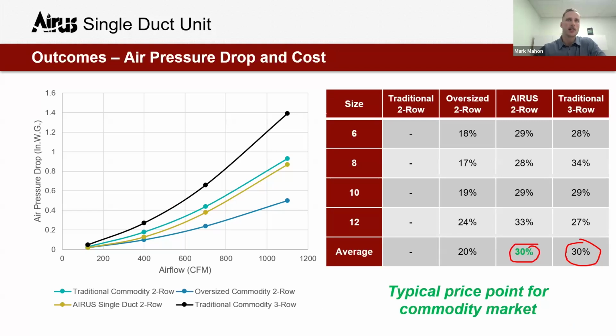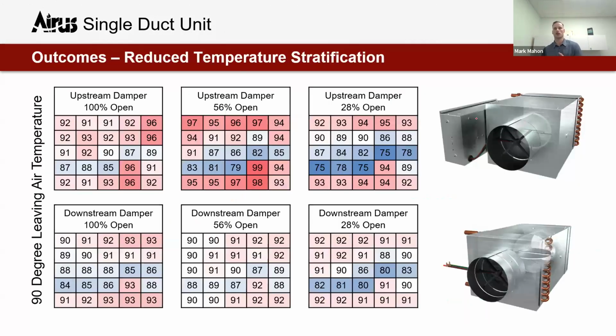So a consideration there. From an air pressure drop perspective, a 3-row coil would be highest air pressure drop in black. A traditional commodity 2-row coil in teal. We see the Aris with an oversized 2-row coil coming in a little bit lower, and an oversized commodity 2-row coil being the lowest. Generally speaking, though, my recommendation is to stay below 2,000 feet per minute, which is 700 CFM for an 8-inch box. And we can see the difference between these two is much narrower. Another good rationale for not putting too much airflow through a box inlet.